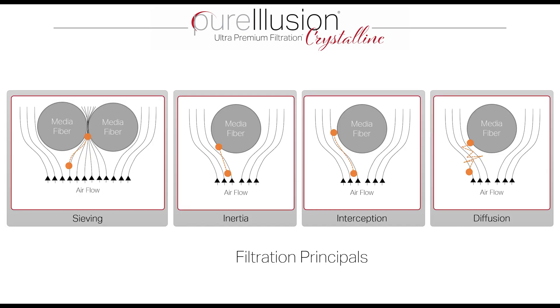How is that possible? It seems counterintuitive. To understand, we need to look at filtration principles, starting with sieving. Sieving is like when we were young on the beach, putting sand in a sieve, shaking it, and watching the sand fall through while larger objects remained on top. But this is not what we do in HEPA filtration, because the particle size would require media fibers to be so close together that it would be very restrictive on airflow.